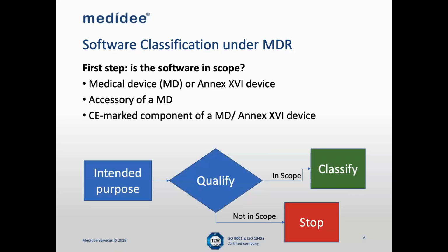For that to happen, it is important to define the intended purpose. The intended purpose is the way, the means of use. It is defined as the use for which the device is intended according to the data supplied by the legal manufacturer. So if a legal manufacturer is claiming that the device can be used for a particular medical purpose, this will become the intended purpose of that product. Based on the intended purpose, the classification of a product is done. If the intended purpose fits into the definition of a medical device, then the product will be classified as a medical device and will be dealt with under the requirements explicitly mentioned within the medical device regulations.